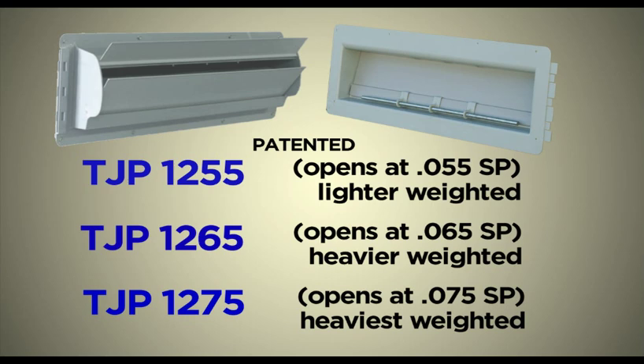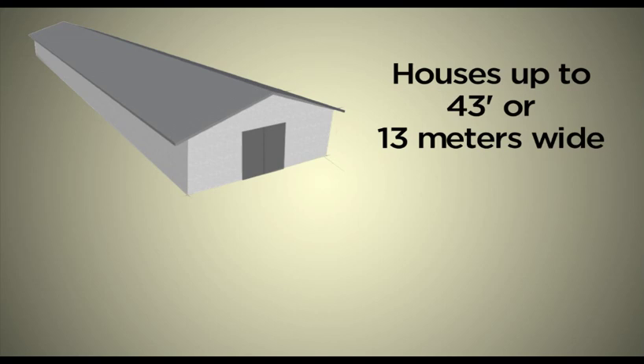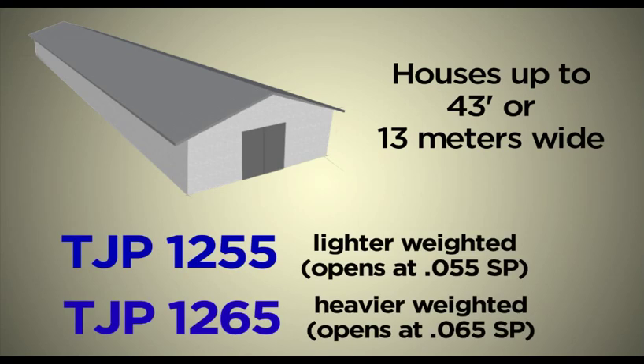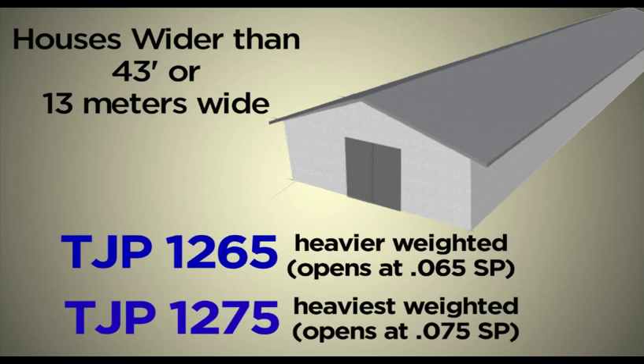You have 3 choices of TJP inlets: the TJP 1255 (lighter weighted), the TJP 1265 (heavier weighted), and the TJP 1275 (heaviest weighted). The heavier the rod, the greater the static pressure (SP) needed to pull TJP inlets open. In houses up to 43 feet or 13 meters wide, use a combination of TJP 1255 (lighter weighted) and TJP 1265 (heavier weighted). In houses wider than 43 feet or 13 meters, use a combination of TJP 1265 (heavier weighted) and TJP 1275 (heaviest weighted).